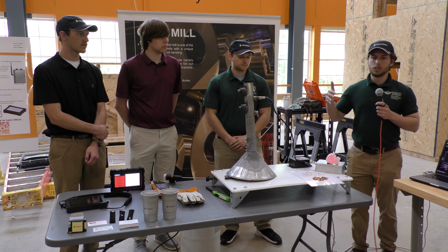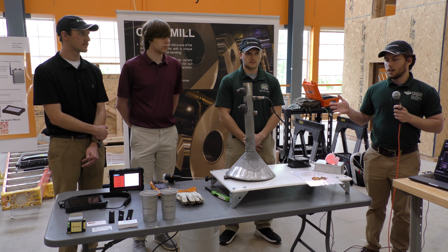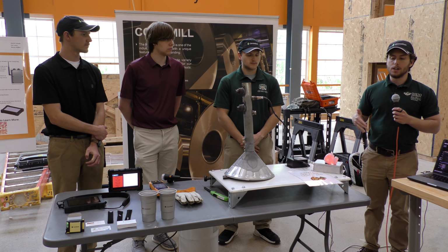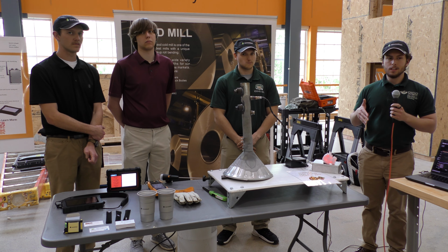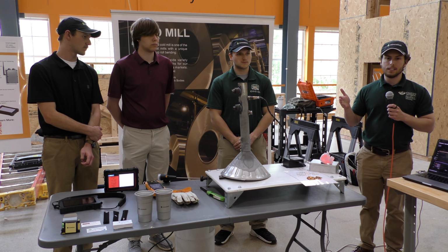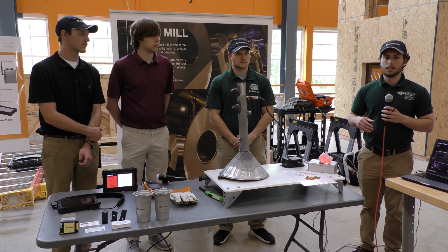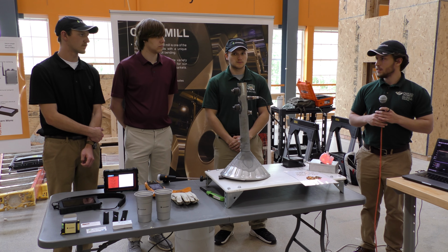That's what we're trying to solve: a lot of these furnaces are out of tune and they're burning not very efficiently. So we're trying to provide them a way to see what oxygen levels are like in the flue gas, so they can tune it to the correct levels and burn efficiently.